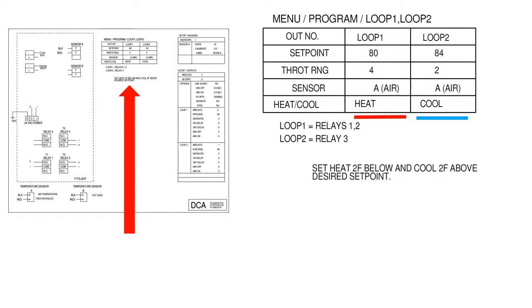The loops must remain as they are. Changing loop 1 to cool would only mean, for example, that a furnace is being activated in an attempt to cool the room. If you need to change the setpoints, the instructions can be found in the DCA installation manual on our website, or you can call DCA. Let's get started.